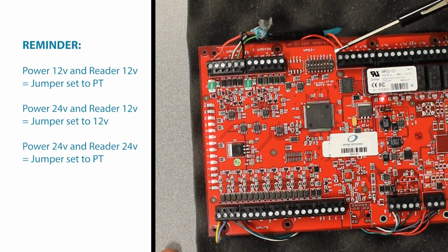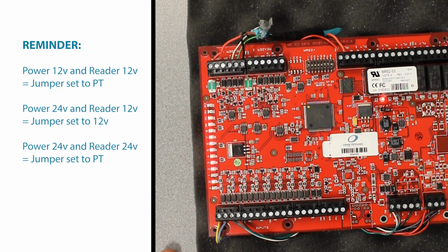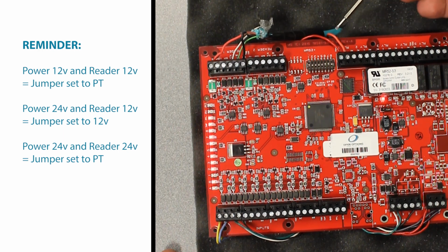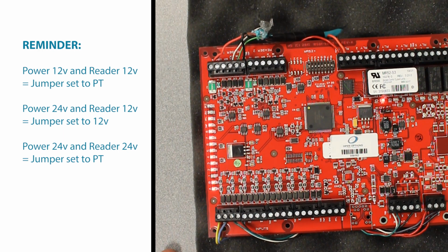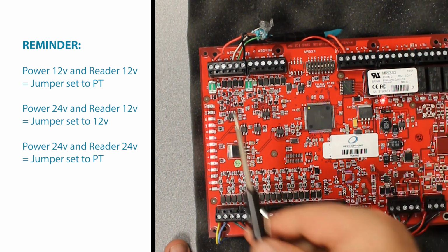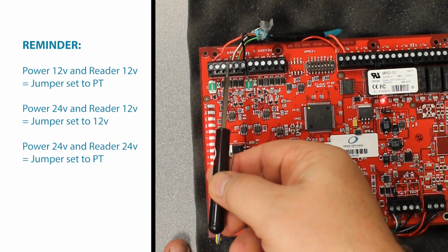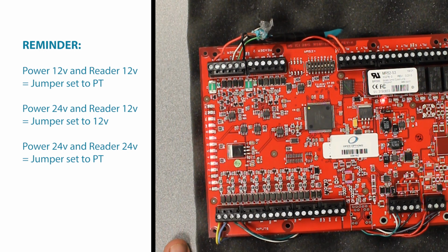On the output, I got 12 volt coming in from my power supply there, 12 volt from the lead from the strike coming into there, the ground from the strike goes back to my power supply ground, and my reader. I've only got data 1 and data 0 wired up. I do not have the LED and buzzer control wired up for this testing.